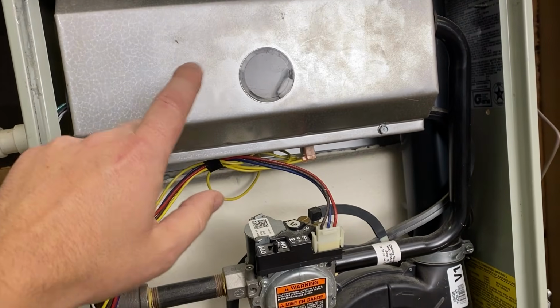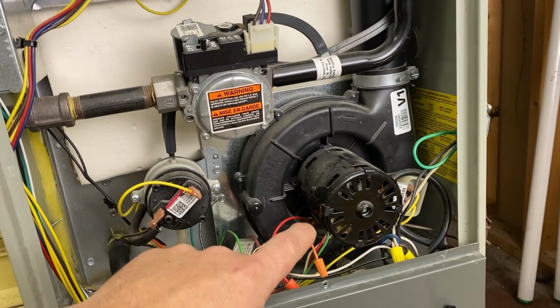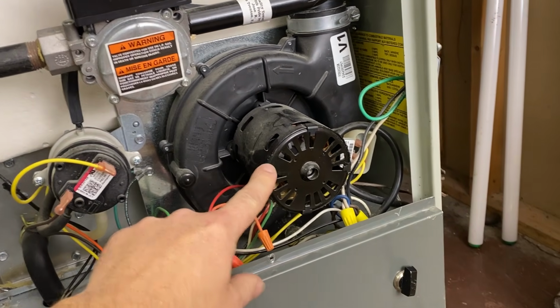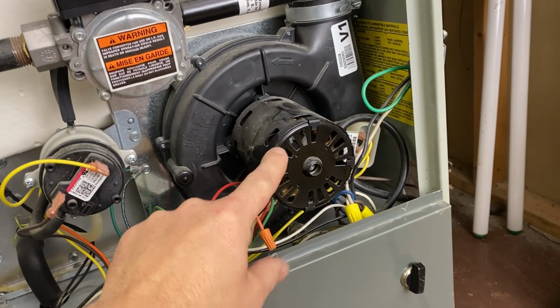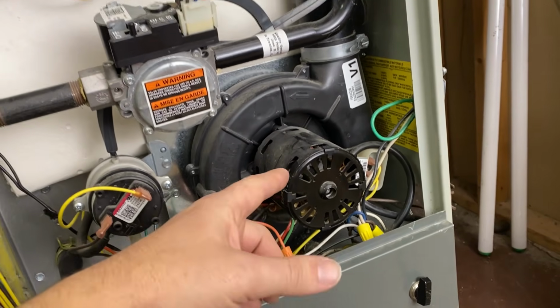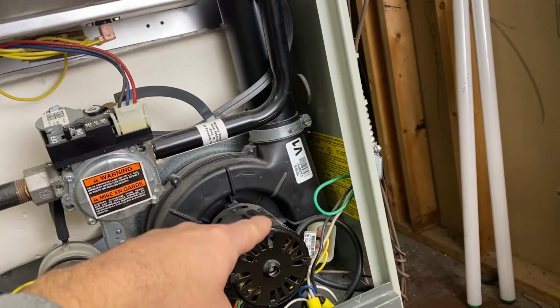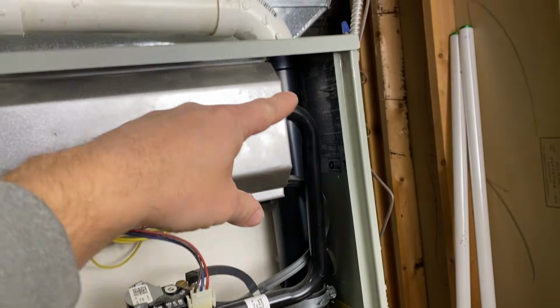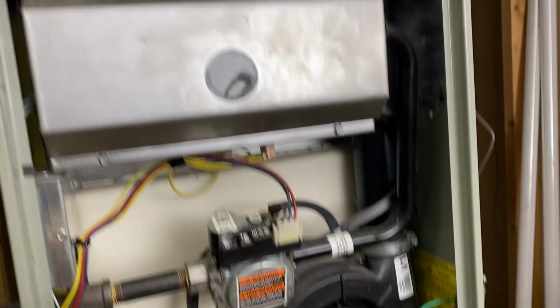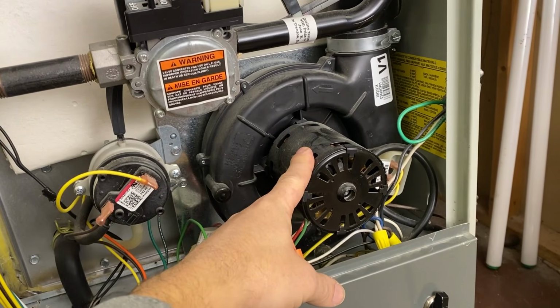What's going to happen here, I'll flip this on in just a minute and show you the problem that I'm having. The first thing that's going to happen is the induced draft motor is going to kick on. This will induce a draft in the exhaust pipe. The blower will turn on, and it just starts blowing air out of the exhaust vent there. This obviously has to be running.